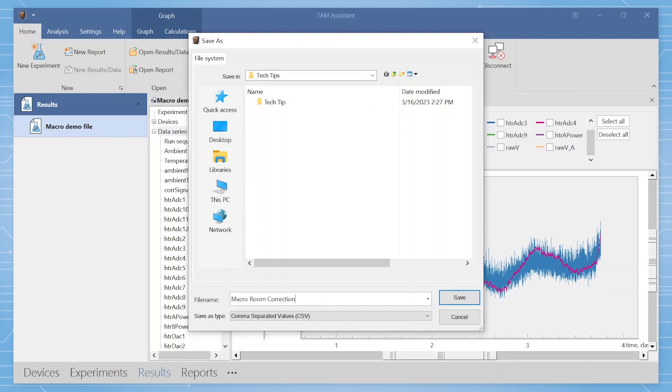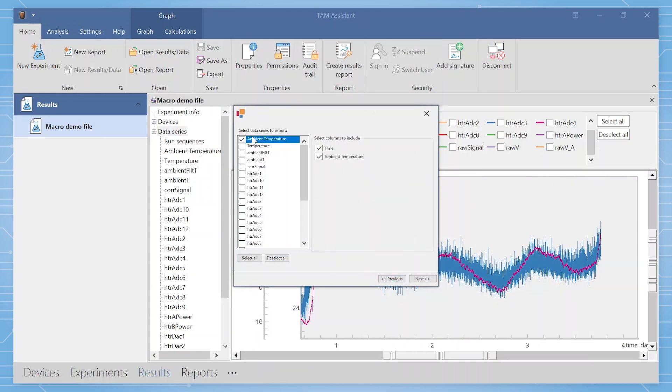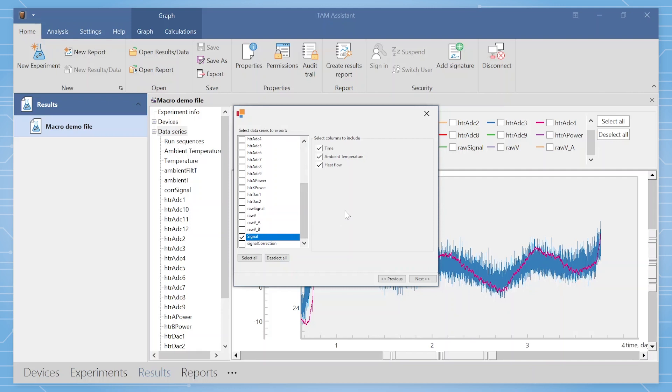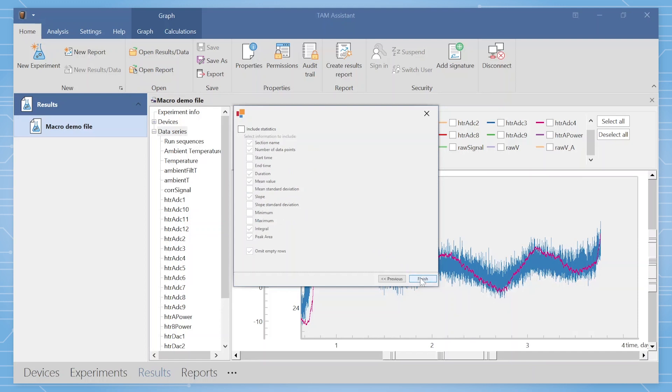A wizard will appear that will allow you to select the data you wish to export. It is recommended to export the ambient temperature and signal, and on the right to include time, ambient temperature, and heat flow. Include the raw data and make sure subtract baseline is not selected. For the time information, it is suggested to export at equal spaced intervals of 20 seconds. Click the finish button.